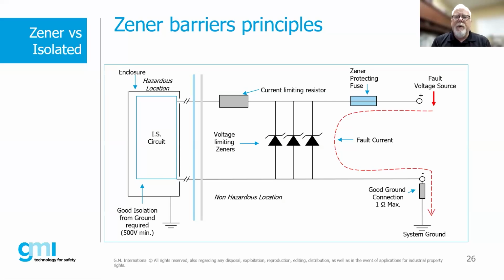So now getting into the isolators and the Zeners. Here's the principle of a Zener barrier. You have a Zener protecting fuse, a current limiting resistor, and voltage limiting Zeners. And we notice that we've actually got 3 Zener diodes. Barbara had mentioned that for intrinsic safety at the highest level, IA, we have redundancy because it's double fault tolerant. And that's why we have multiple Zener diodes on the inside of this barrier.